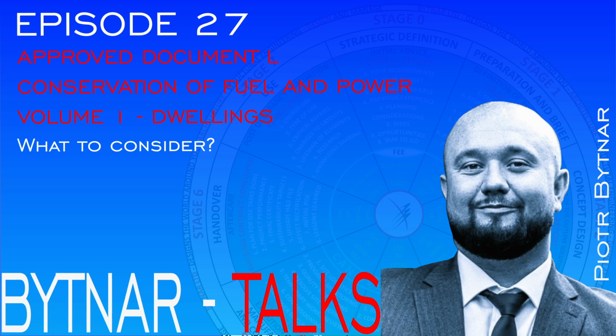The requirements are similar to that of gas heating systems. We again deal with efficiencies either to ErP or SEDBUK that are set within the document, like for wet heating for regular boilers being 91 ErP or 84 SEDBUK, and so on. Electric space heating systems. These are considered 100% efficient, so no limits are given. For electric storage heaters, we need to be able to control the input charge as well as the heat release. Electric panel heaters or electric warm air systems also need control for each room or the appliance, but check the requirements of section 5 to not go too crazy on the amount of control.